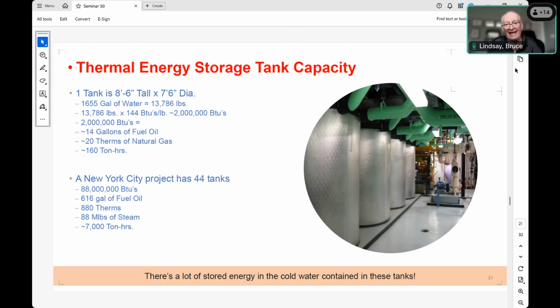Real interesting. The tank is 8 feet in diameter. It's 8.5 feet high, and it holds roughly 14,000 pounds of water. When we freeze that water, we have to extract 144 BTUs per pound. It goes from 32-degree water to 32-degree ice. And that latent heat of fusion, 144 BTUs per pound, times 14,000 pounds, each tank can supply 2 million BTUs of heat. Okay, and you have a lot of these tanks in some of these buildings. It's going to be incredibly impressive. Just remember, there's always a lot of stored energy in the cold water in those tanks.